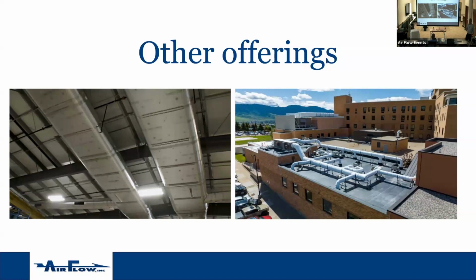I want to redo some of our system here and I'm like, oh my God. I can take down ceiling tiles, no big deal. But taking out the ductwork and putting new ductwork in because we have a plenum return, oh my God, it's surgery. So that ductwork really ought to stay there forever. Over time, with heating and cooling, it's going to expand and contract, and how good is our sealing job? Well, day one, if you don't pass the test, how bad is it going to be in 5 years? It's going to be pretty bad.